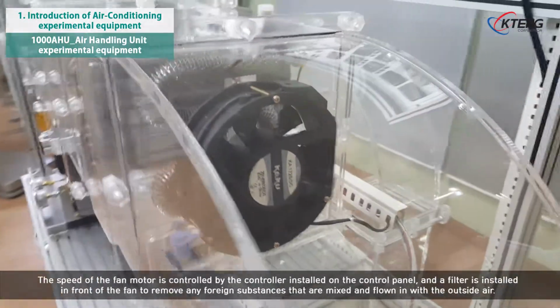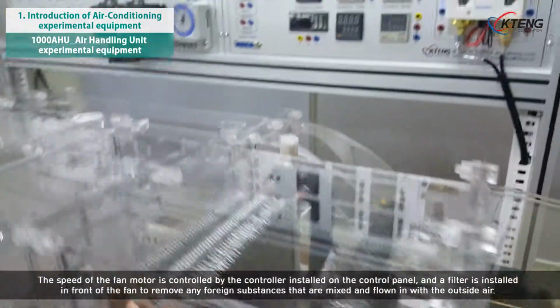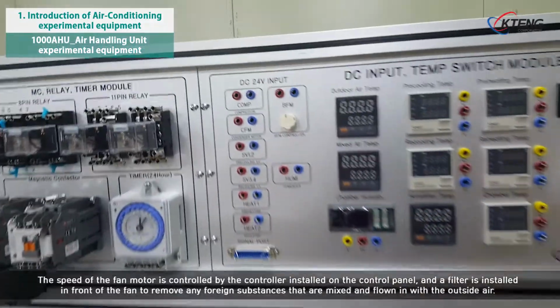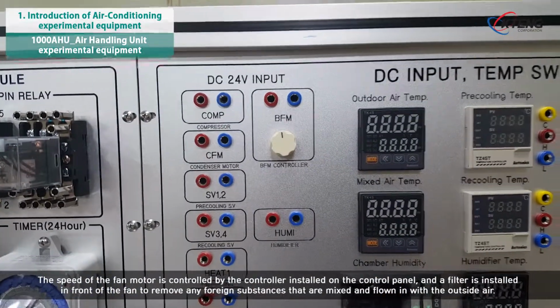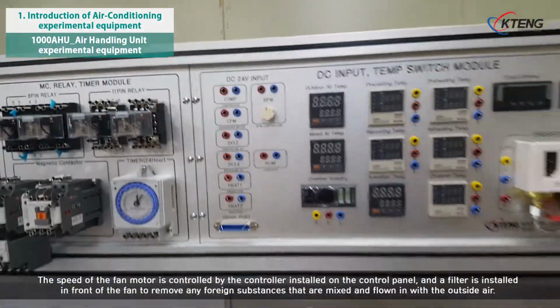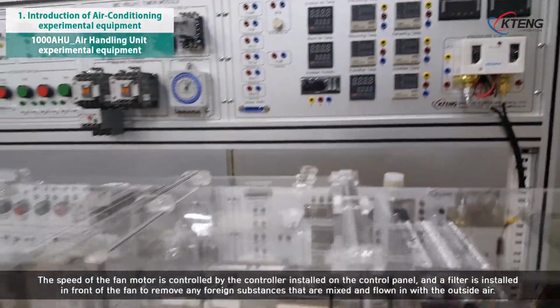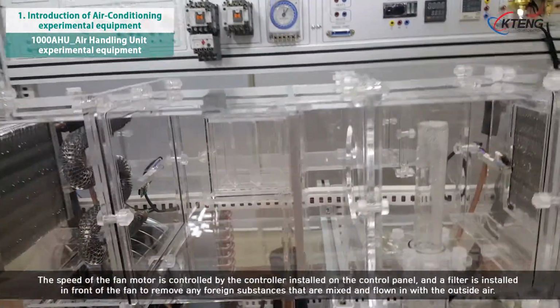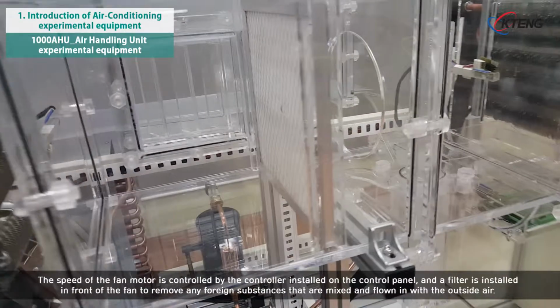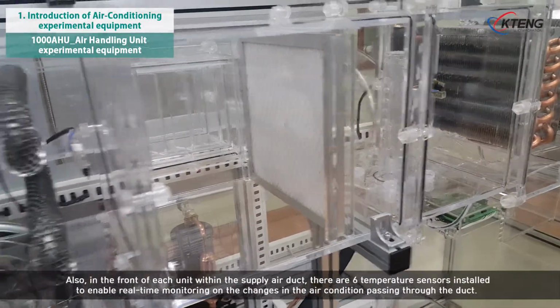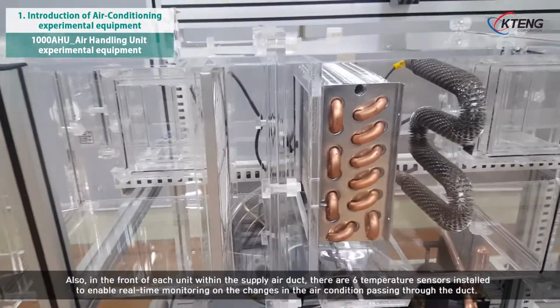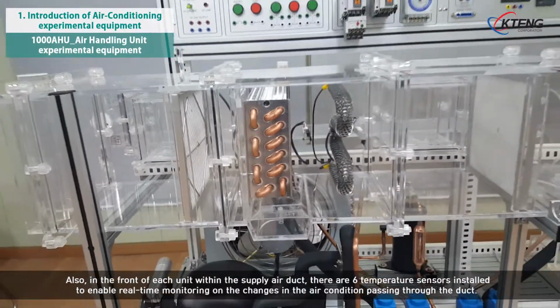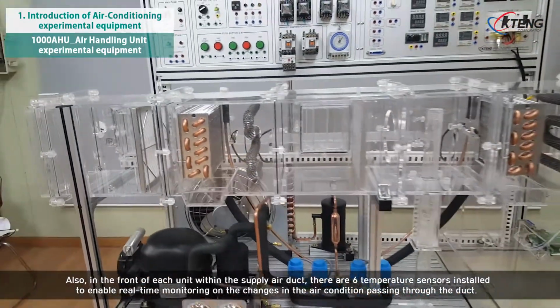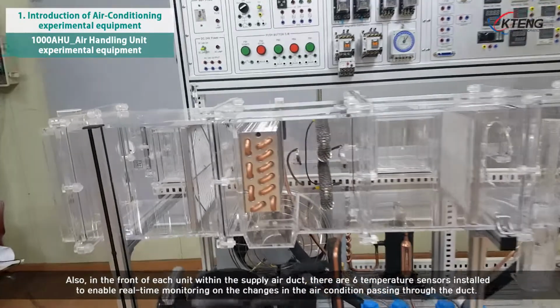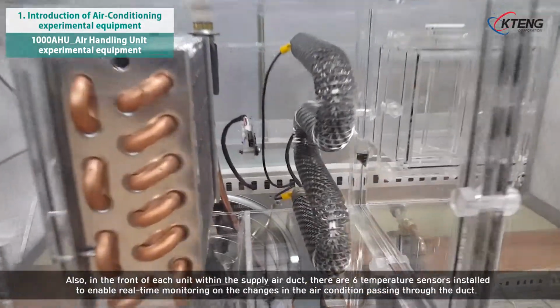The speed of the fan motor is controlled by the controller installed on the control panel. And a filter is installed in front of the fan to remove any foreign substances that are mixed and flown in with the outside air. Also, in the front of each unit within the supply air duct, there are 6 temperature sensors installed to enable real-time monitoring on the changes in the air condition passing through the duct.